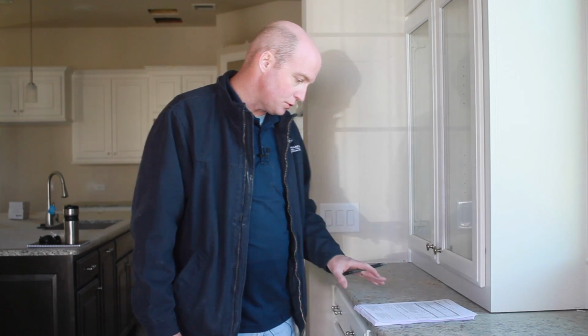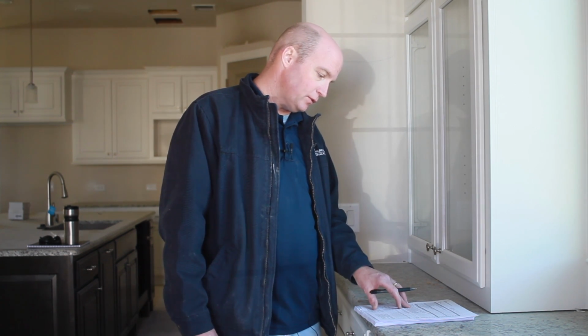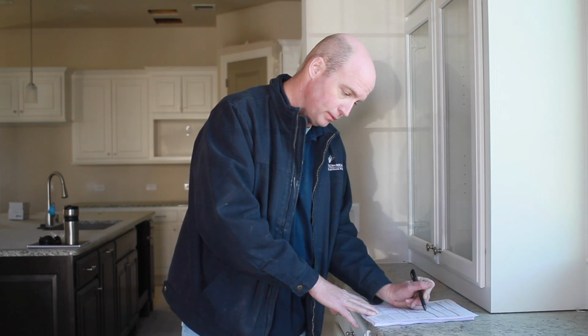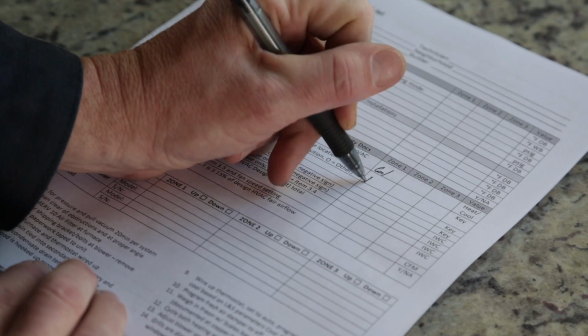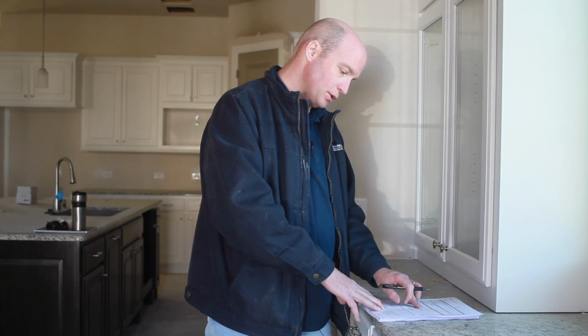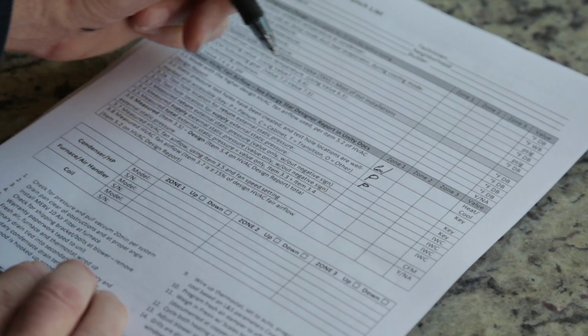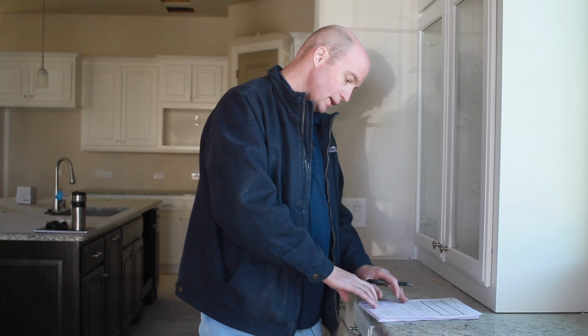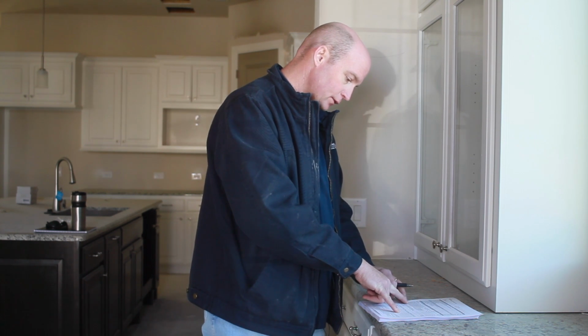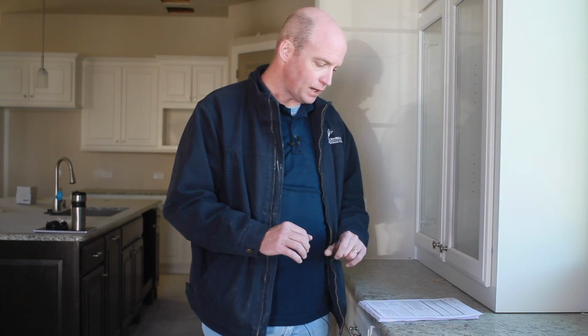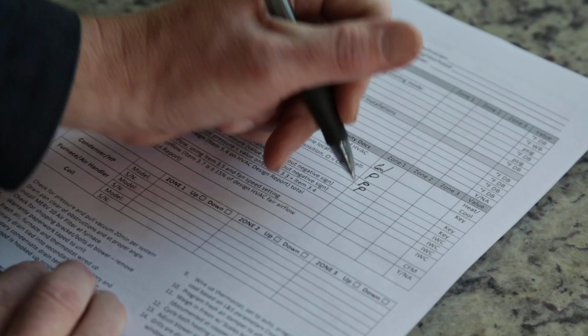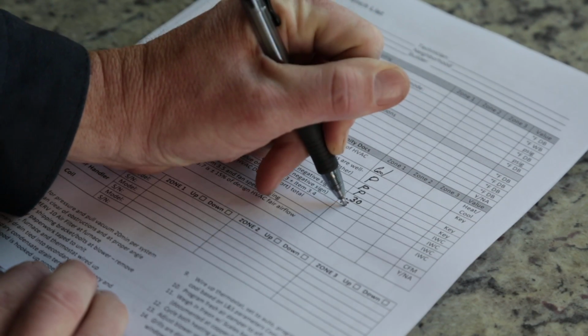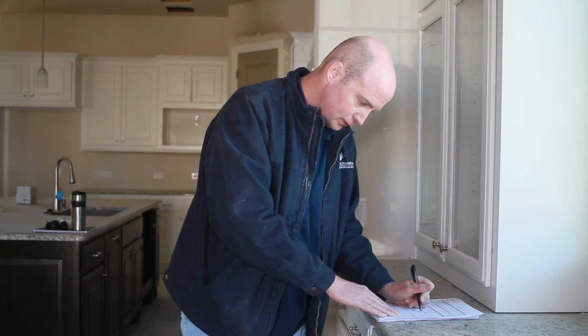Number 3.2, static pressure test holes have been created, well marked and accessible. And where are they? Well, in this particular test, we used the plenum. So we'll simply mark plenum. Just put a P. Test hole location for external static pressure. Test hole location for return external static pressure. Well, for both of these, we'll put P down as well again. Now, measured external static pressure, value only without the negative sign, and measured supply external static pressure, measured value only without the negative sign. Remember, there are no negatives and positives. In this case, our total external static pressure, we were running 0.65. So one of them was running at, I believe it was the external return was running at 0.30, and our supply was 0.35. Then our total, we simply add those two together. Our meter did the same thing. It was 0.65.